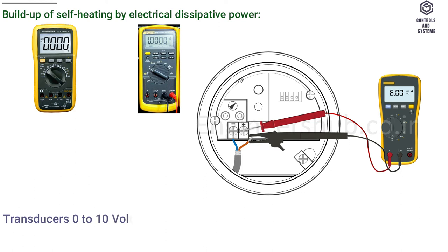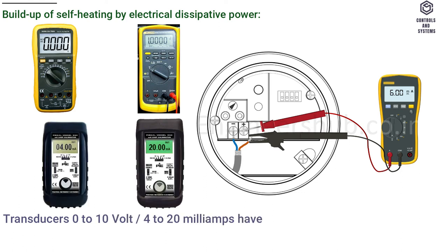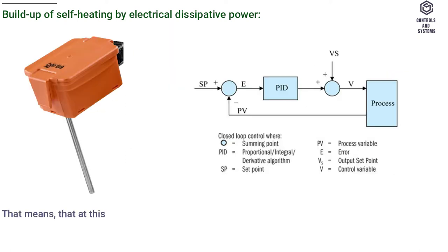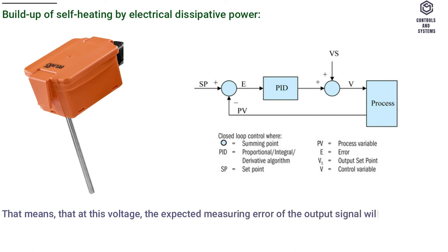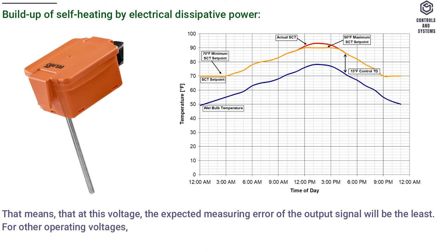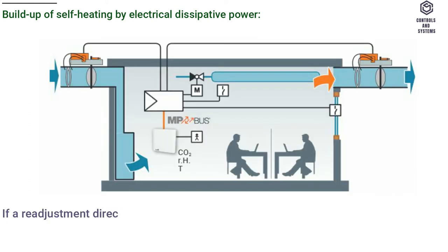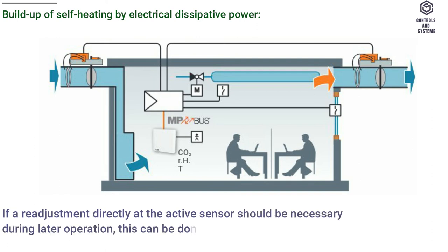Transducers 0 to 10 volt and 4 to 20 milliamps have a standard setting at an operating voltage of DC 24 volt. That means that at this voltage, the expected measuring error of the output signal will be the least. For other operating voltages, the offset error will be increased by a change in power loss of the sensor electronics. If a readjustment directly at the active sensor should be necessary during later operation, this can be done with the following adjustment methods.